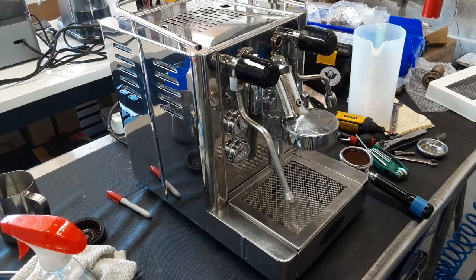So what I did is we took it out completely and replaced the air valve on this machine. Since it was a new pump, I went with the compressor and tried to unclog it, which I was successfully able to do. I don't know if I got all of it out. We did descale this machine, so hopefully that broke a lot of it down that was inside the pipes and stuff like that. But I compressed it a lot, and it finally gave up and shot a lot of it out, so I didn't have to replace the pump.